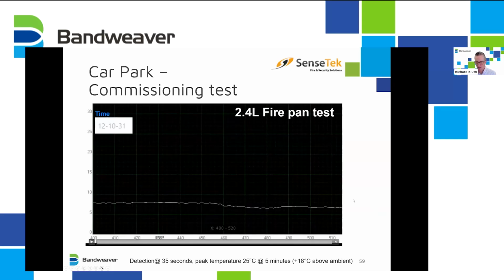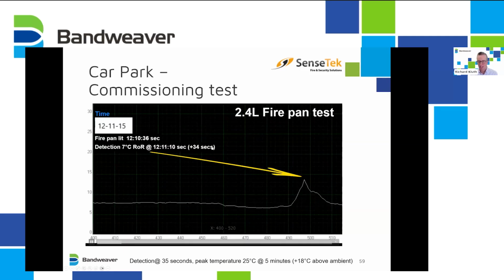You've got the distance along the fiber here, and you can see the heat developing. This is the time at the top. So you can see here, it starts at 5 seconds, the fire's lit. You can see the fire starting to develop. Here, in this case, it was set to 7, the rate of rise. So it detected at 34 seconds for this particular example.